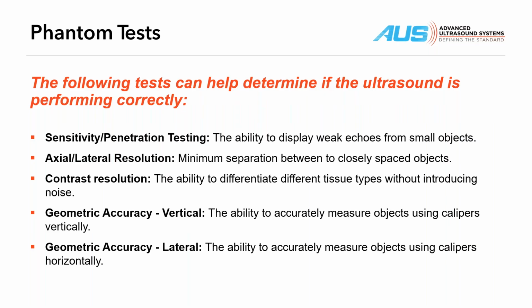We're going to talk about system sensitivity and penetration testing. Don't let the word sensitivity bother you. It is penetration testing. We're going to use the ability of the ultrasound system to display weak echoes from small objects. And I'll show you a picture. We'll describe how you use a phantom to do sensitivity / penetration testing. Again, people often get confused about the sensitivity. It is just penetration testing, okay?